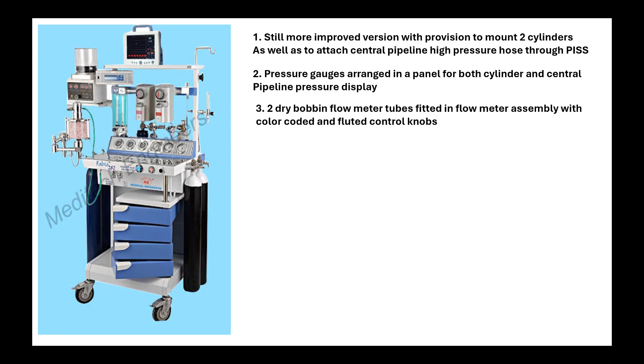So the pressure gauges are arranged in a panel in front, and there is a display for both cylinder as well as pipeline pressure. That is an improvement that has been made. And again, there are two dry bobbin flow meters fitted with the assembly, and they are color coded. And two Tec vaporizers are there in the back bar. One may be isoflurane, or one may be sevoflurane.